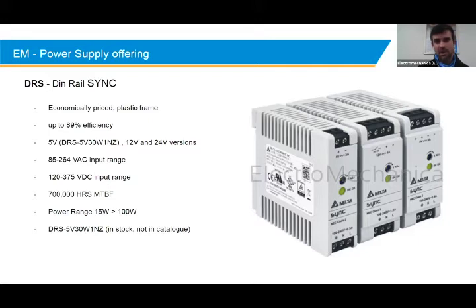We've got the 12 and the 24 volt versions in our catalog, as well as one that's not illustrated, that's a fairly new addition, the 5 volt DRS with this part number that I'm highlighting over here. So that's a 5 volt power supply, also in stock in the DRS range. It's got a wide input AC range, 85 to 264, as well as DC input range. Very high mean time before failure, over 700,000 hours. And our power range is relatively small, only 15 to 100 watt. So that's the DRS.